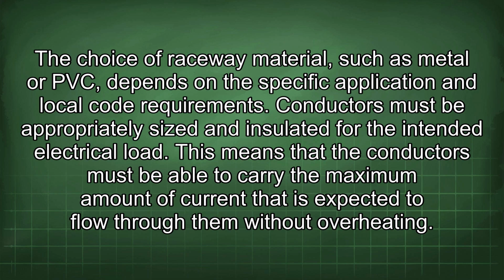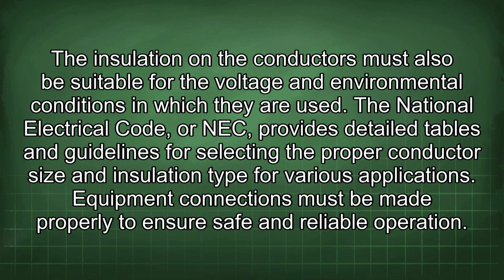Conductors must be appropriately sized and insulated for the intended electrical load. This means that the conductors must be able to carry the maximum amount of current that is expected to flow through them without overheating. The insulation on the conductors must also be suitable for the voltage and environmental conditions in which they are used. The National Electrical Code, or NEC, provides detailed tables and guidelines for selecting the proper conductor size and insulation type for various applications.